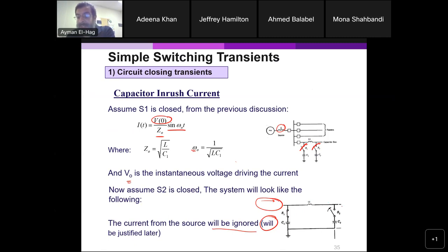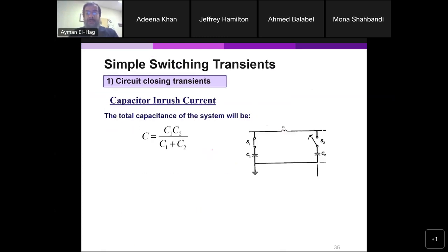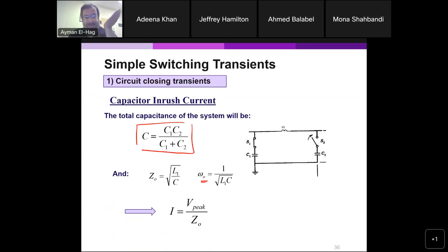Now we'll see what is the impact when I connect another capacitor here, how this will impact my system. So now the total capacitance, assume these two are in parallel, so they are C1 C2 over C1 plus C2. As a matter of fact, those capacitors will be in series, not in parallel. When we have capacitors in series, this is how we find the total capacitance. Now your surge impedance has changed, it becomes the square root of L1, not L, divided by the combination of the capacitors in series, and this will be your frequency. So we'll see what is the impact on this frequency. And your current is the same thing, the V peak divided by Z0.